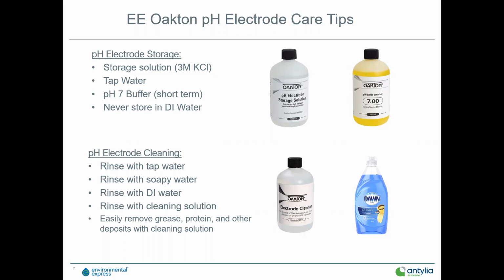Never store your pH electrodes or ORP electrodes in distilled or deionized water. That will literally leach the electrolyte out of the electrode into the storage solution, and it'll go from 3.8 molar, 4 molar, down to less than 2, and that electrode will literally be done.